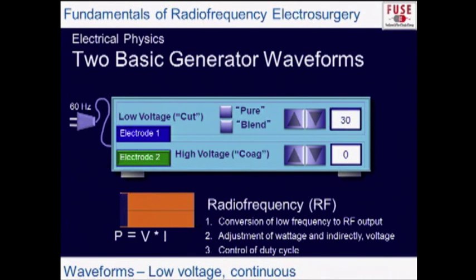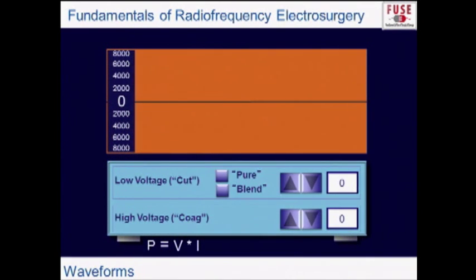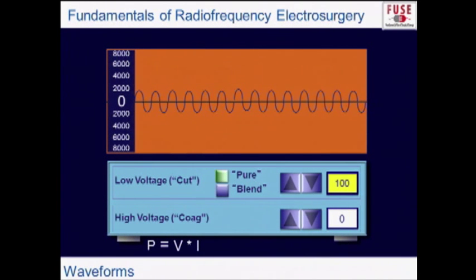There are basically two waveforms produced by generators. The first is the so-called cut mode — a low-voltage, continuous output. If we set it to pure cut at 30 watts and view it on an oscilloscope, we see a continuous sine wave. Turning it up to 100 watts gives the same sine wave with higher voltage — the peak-to-peak voltage increases. The voltage oscillates around zero, and the sum of the positive and negative peaks is the peak-to-peak voltage.